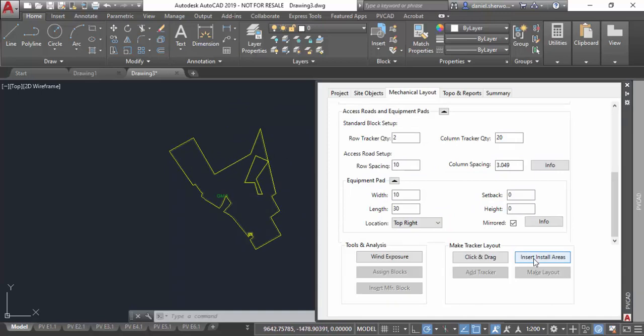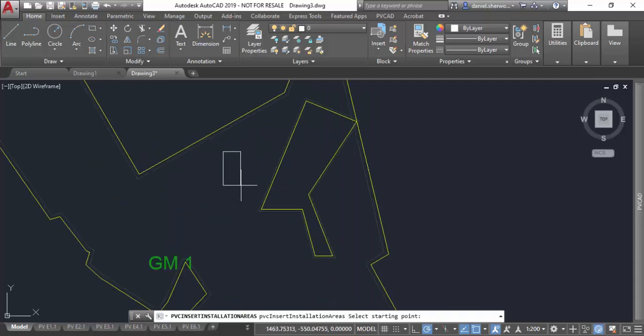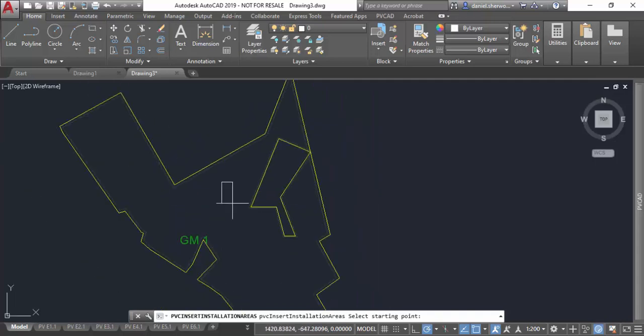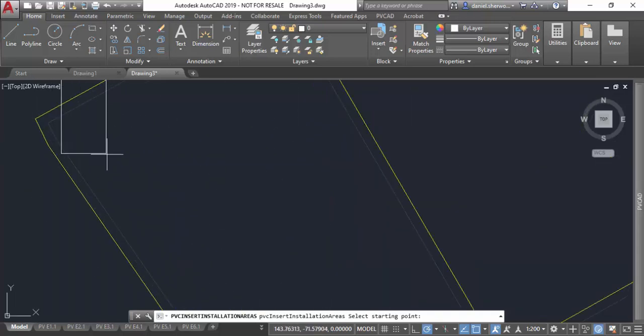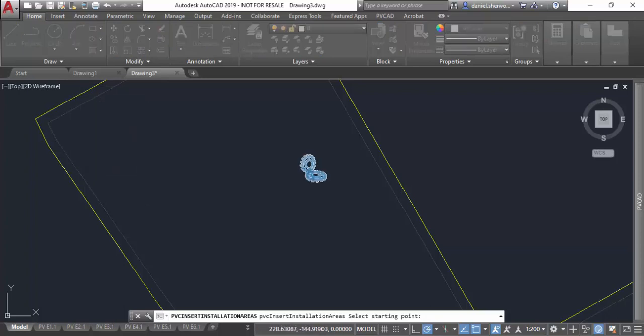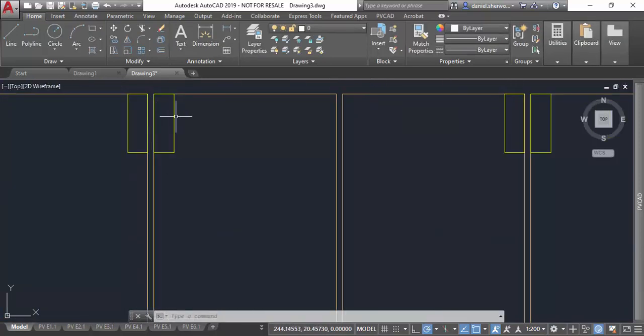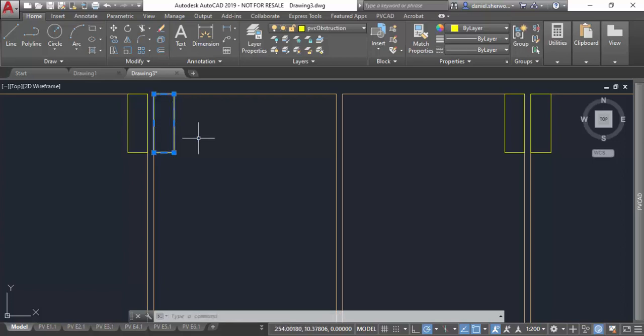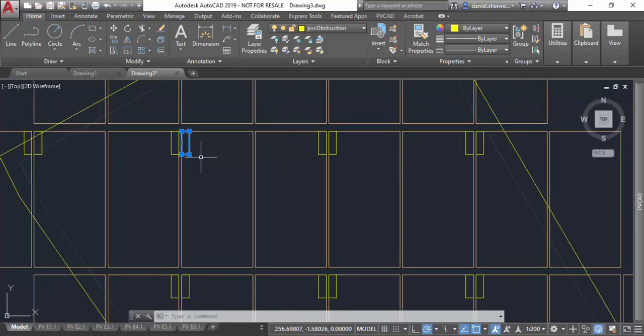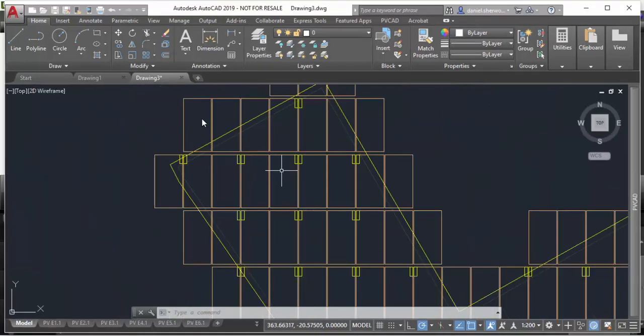When all that is done I'm going to insert installation areas—that's what we call our standard blocks. This is the size of one: two trackers up by 20 trackers across. You can see that when I do my layout of my standard blocks it leaves the equipment pads in the corners and mirrored as I specified. You can also see that I have an access road of 10 meters in my east-west direction, and in the north-south direction the access road just preserves the row-to-row spacing.